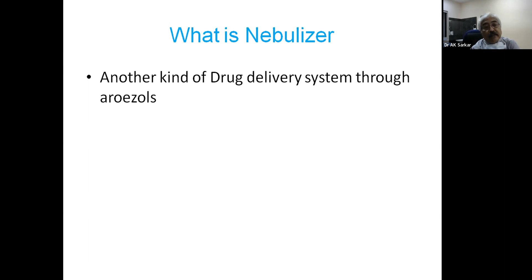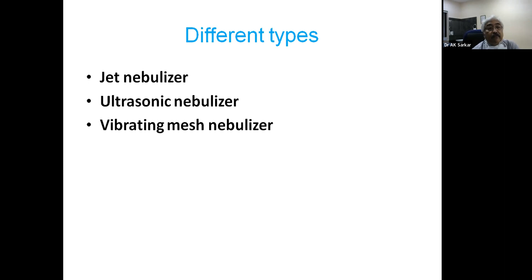Right now we have 3 different types of nebulizer available for our use. The jet nebulizer is the most commonly used nebulizer throughout the world. And of course, we have started using the vibrating mesh nebulizer, particularly in critical care. Another mode of giving nebulization is the ultrasonic nebulizer. There are some advantages and disadvantages of those. Coming to the jet nebulizer, the aerosol is produced by compressed gas and the Venturi effect. Therefore, this nebulizer has a very high residual volume, so you need to use more volume for production of the aerosol.